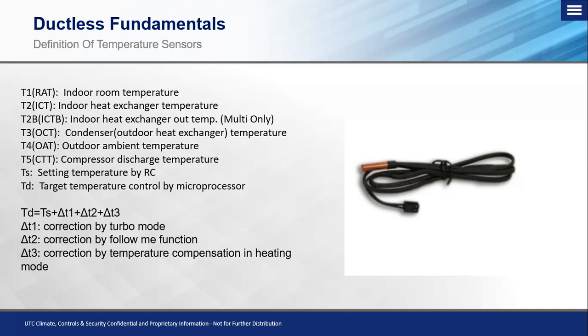Okay, now there are three correction factors you'll see below. You have your delta T1, T2, and T3. These aren't the only correction factors, but these are going to be the most common that we come across. So the first one is going to be your correction by turbo mode. Turbo mode is a feature that is on the wireless remote controller. Now, when you initiate this feature, the turbo mode is essentially looking at the sensible load in the space, not the latent. Ductless systems by nature are sensible load carriers.